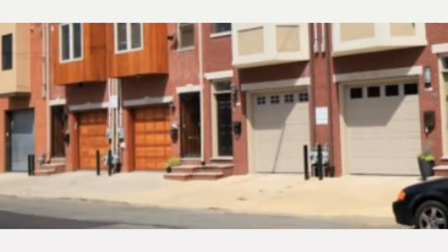But when I go in and replace problems, it was funny. Yesterday, we were at a project where it had common garages, and they had a problem in one plug, and all of these garages were on the same circuit. Nobody could get out of their garage. And what we found was exactly what you say. Somebody had stabbed a wire into one of these quick click plugs. And 20 years later, it had gotten out of there and had pretty much kept, I think, 8 people out of their garage. They had to manually open the garages. Right. Yeah, so that's why we don't let our guys do that. We use the screws on the side.